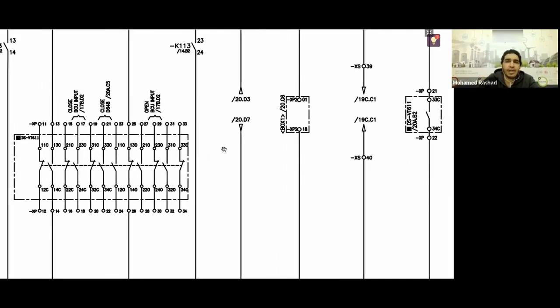33C and 34C are its terminals. What are 33C and 34C normally? Normally open contacts. So when the VT isolator is closed, this contact is also closed. This means that the VT isolator, according to rule number 5, is depicted in the drawing as being open. Therefore, all its contacts that you find in the drawing are referenced as if the VT isolator is open. So when the VT isolator closes, this contact closes.